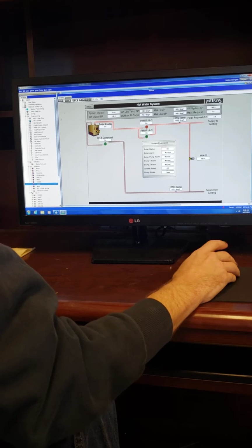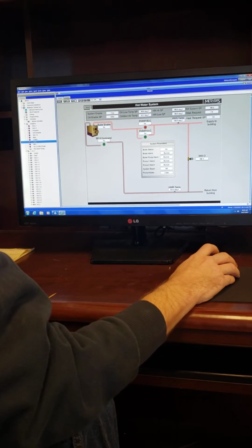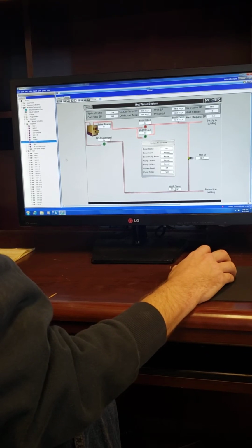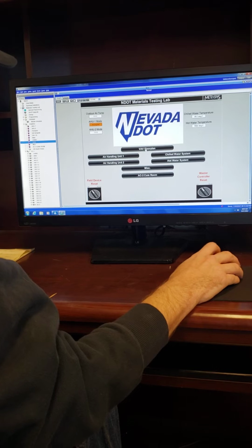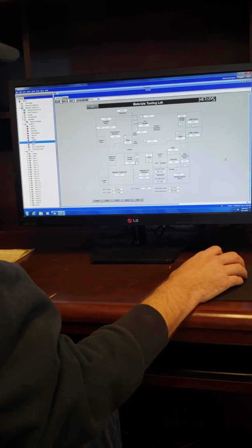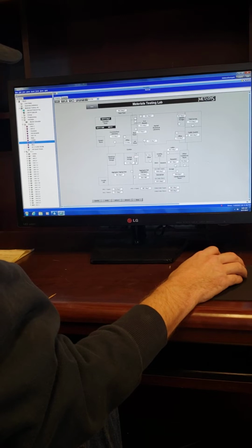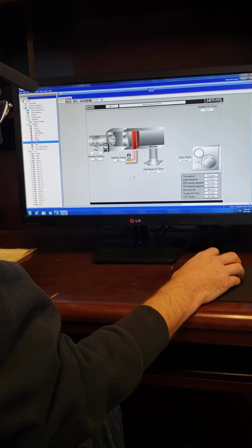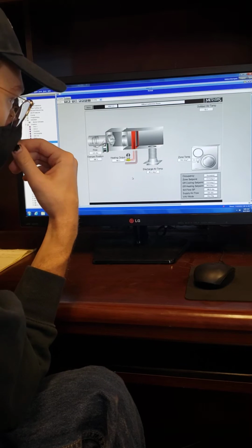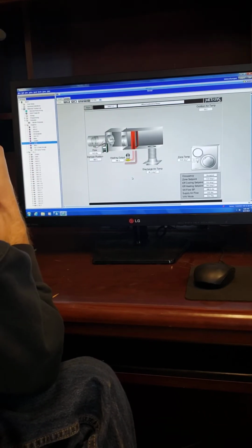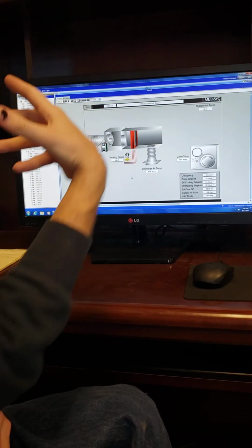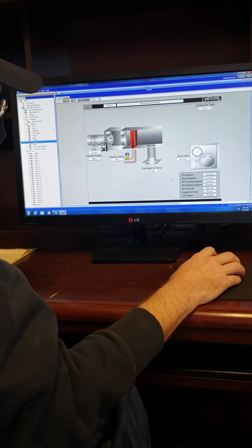So either I want to shut this one completely down, or maybe just a little bit open. That's one of the cool things about these VAVs, they modulate both the airflow and the hot water output, so we can kind of tune this. I'm going to want to actually pop up and take a look at your unit, because it says your damper is 100% open and we're not reading airflow. But obviously you're getting some airflow, or we wouldn't be warming up in here.